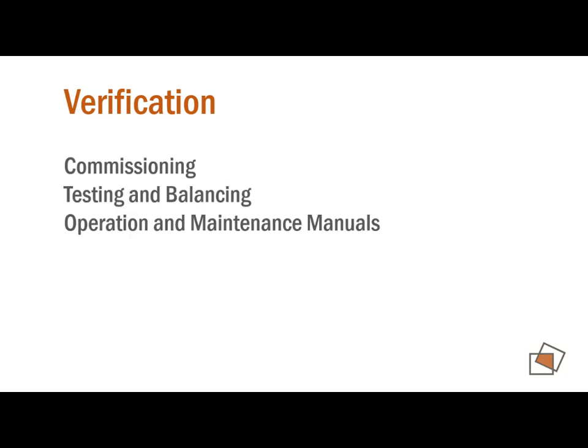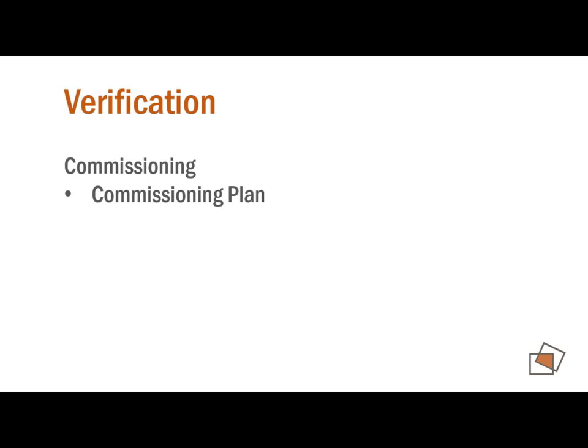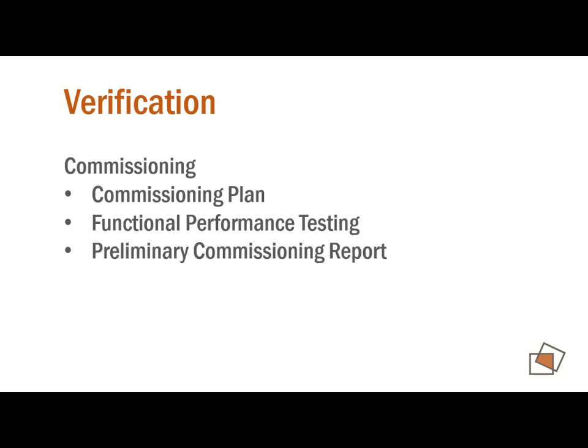So let's look at what's involved with commissioning. This is what the energy code says you have to do. First off, commissioning applies to HVAC systems and service water heating systems per the energy code. It's not uncommon for a commissioning agent to commission the lighting control systems, but that's not required in the scope of the energy code. For what the energy code says you have to do, you have to have a commissioning plan and functional performance testing. After the systems are in there, you're going in, taking temperatures, and making sure that the unit's heating when it's calling for heating and cooling when it's calling for cooling, that a hot water recirc pump is shutting off when it's supposed to, these types of things. Then you prepare a preliminary commissioning report.